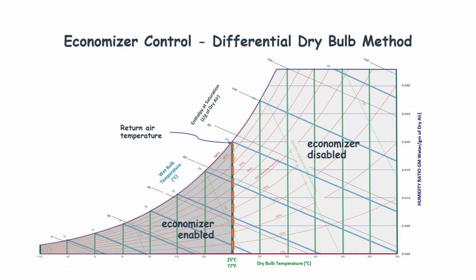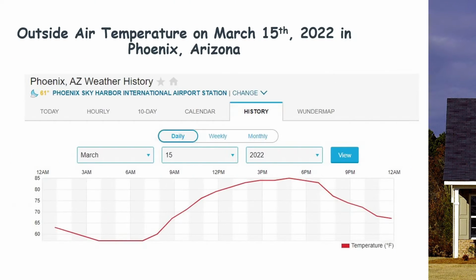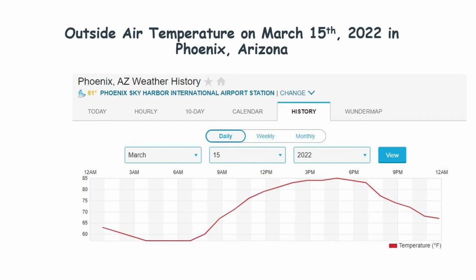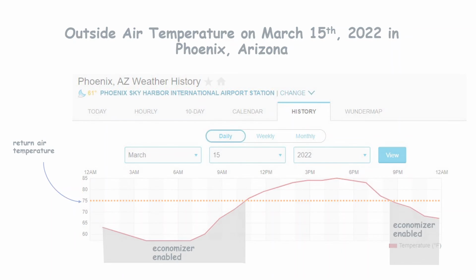The advantage of this method is that we are sure that the outside air will never increase the cooling load, even when the occupants lower the room's cooling set point. As an example, let's look at a house in Phoenix, Arizona on March 15th of 2022. Let's assume the indoor temperature set point is 74 degrees Fahrenheit. The mechanical cooling system turns on to cool the room when the room's temperature or the return air temperature increases to 75 degrees Fahrenheit. Now, the controller activates the economizer whenever the outside air temperature is below 75 degrees Fahrenheit.